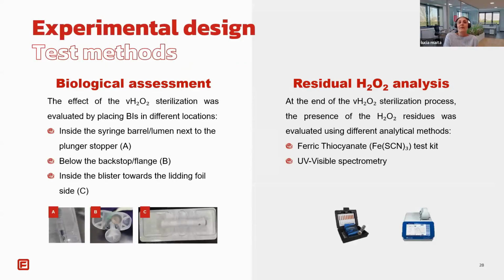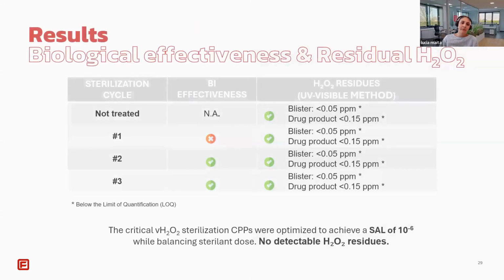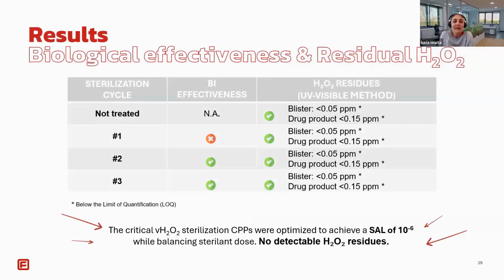As for the previous case study, the process effectiveness was evaluated using biological indicators placed in the worst case position, and in parallel, the residual amount of H2O2 was assessed using both a screening and a confirmatory analytical method. This approach ensures the evaluation of both sterilization performance and safety aspects. The results show that across all the tested cycles, biological effectiveness was achieved for cycle number 2 and cycle number 3, with no growth observed after 7 days of incubation for the biological indicators.